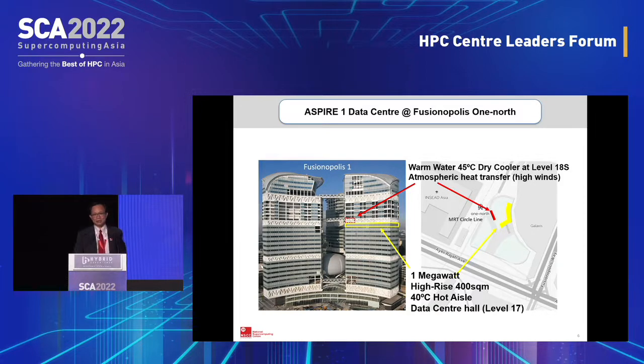Our data center hall lives at this high location for various reasons I won't belabor. We make use of warm water cooling because Singapore's temperature spans between 25 degrees in the cool 4 a.m. hours up to as high as 35 degrees during the day. Still, our warm water used to extract heat from our hot chips can expel heat at 45 degrees, giving a sufficient temperature delta to provide the heat gradient needed to extract heat to the atmosphere.